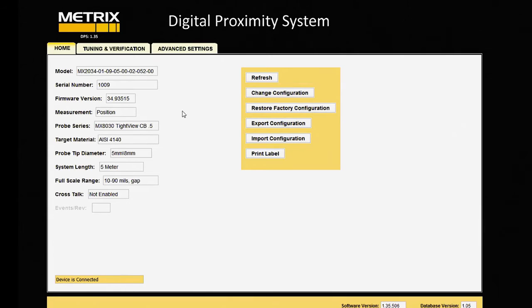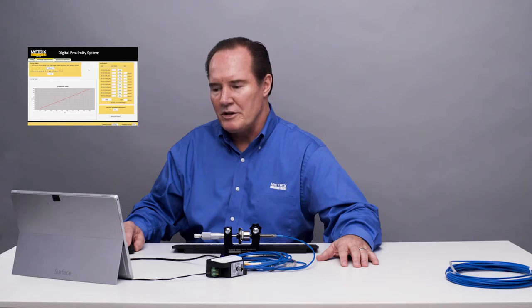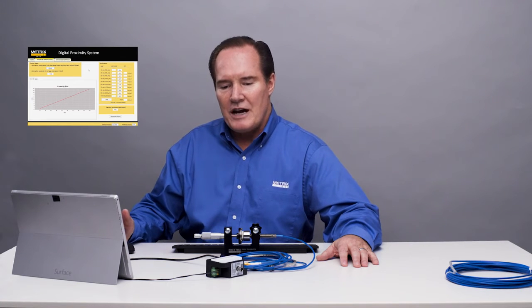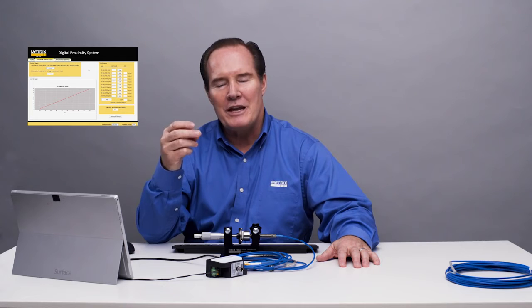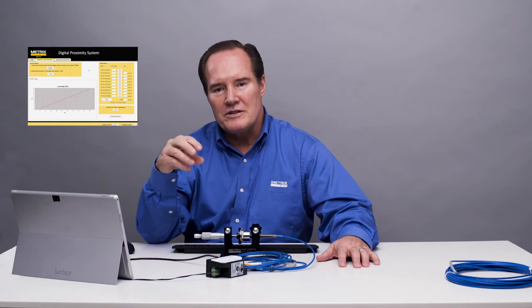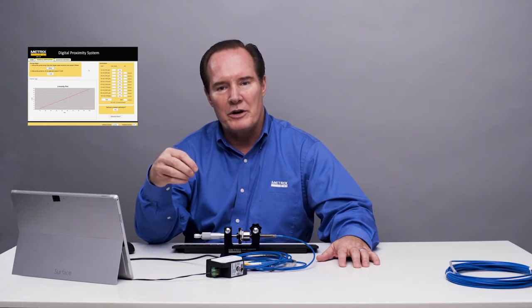Now we're going to do a tuning and verification step to make sure it's working. In this case, we're not going to tune it, just because the way the TightView system works is it's tight in the machine. It's unlike you're going to have a fixture. So we've made it for a tight situation. That's what you have. Now we're just going to test for linearity, see how close we are. I'm also going to demonstrate, if there are any issues, we'll do a custom calibration. So we'll see how that works.